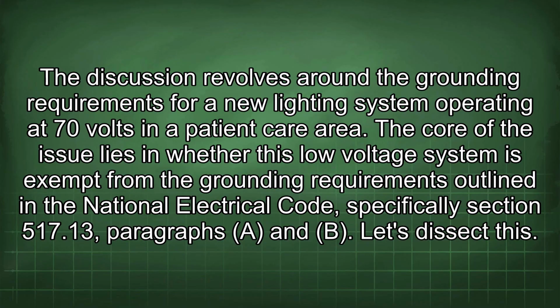The discussion revolves around the grounding requirements for a new lighting system operating at 70 volts in a patient care area. The core of the issue lies in whether this low-voltage system is exempt from the grounding requirements outlined in the National Electrical Code, specifically Section 517.13, paragraphs A and B. Let's dissect this.